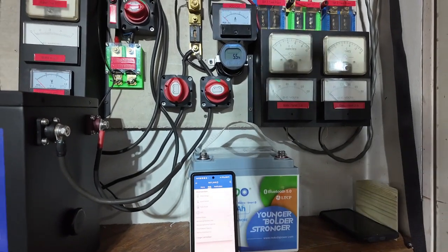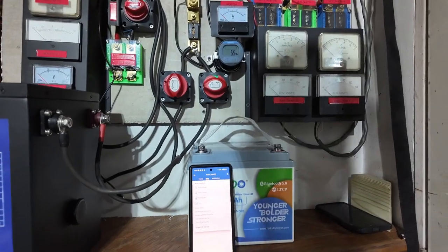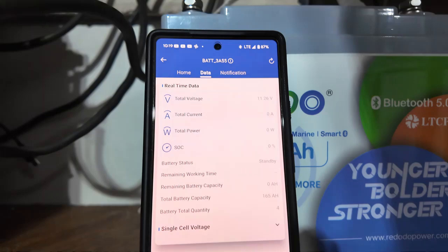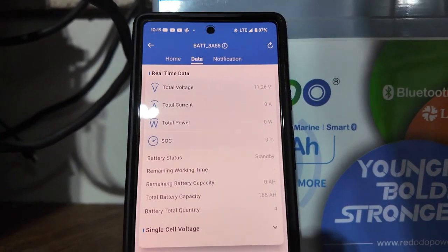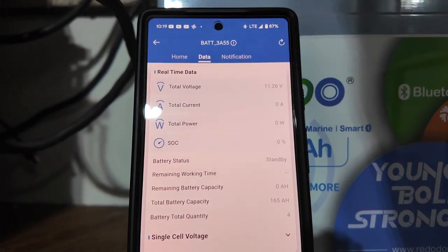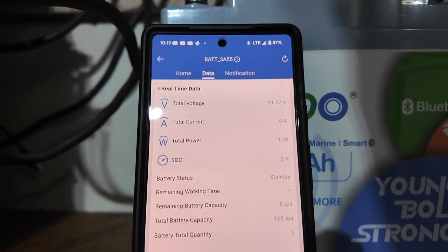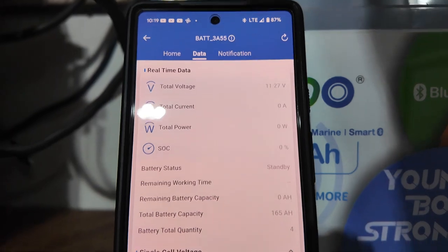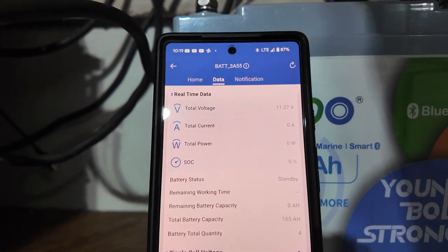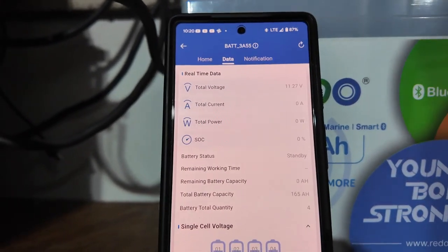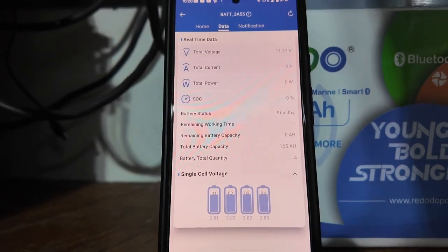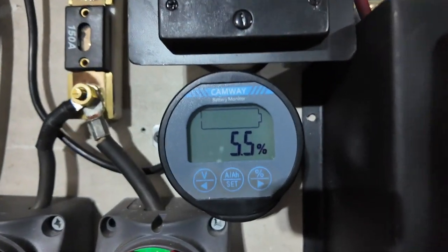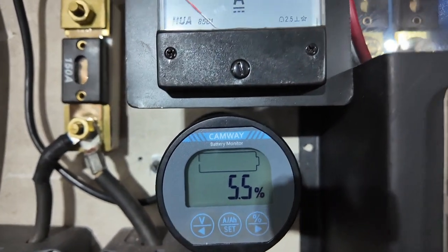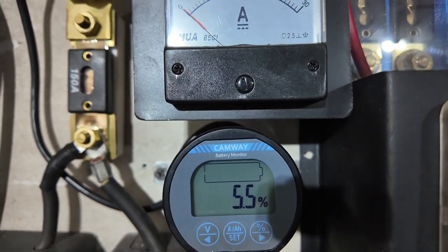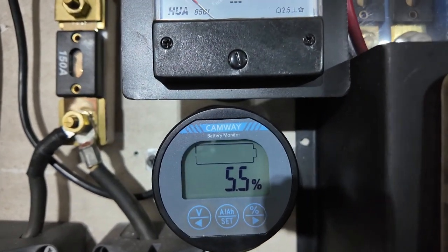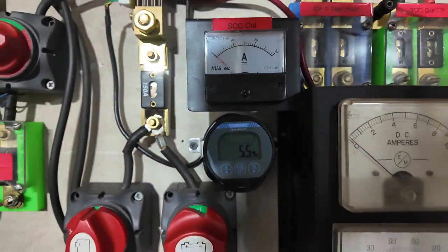I come out to check it, and the inverter was beeping, and the app says 0 ampere hours left. Total battery capacity 165. Let's look at those cell voltages: 2.81, 2.81, 2.82, and 2.85 I think. And it says 5.5, so we set it for 5 extra. I'd say it passed its capacity test for the first time out.